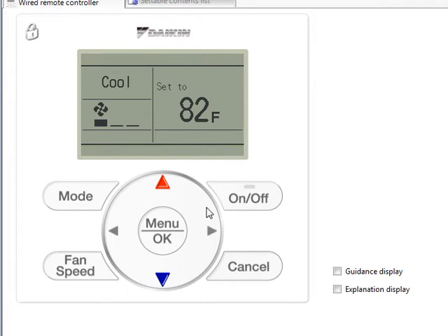When you press any button on this wall controller, it will turn the backlight on. With the backlight on, the first fan coil that you touch the mode button on, the flashing icon will go away. The remaining wall controllers in that system will have the master controlled icon on steady.